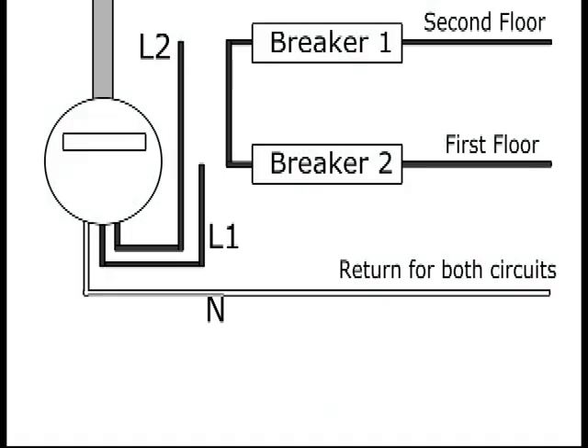Suppose the user decides to change his contract to 220 volts. His meter is replaced by a different one, which delivers three cables. One of them, shown in white, is the neutral, which was already there in the 127 volt connection. And also a pair of black cables, each one of them a live cable, but coming from different power lines in the distribution network. These two black wires are known as phases, or as L1 and L2. If we now take a voltage reading across the neutral and one of the phases, we will read approximately 127 volts.